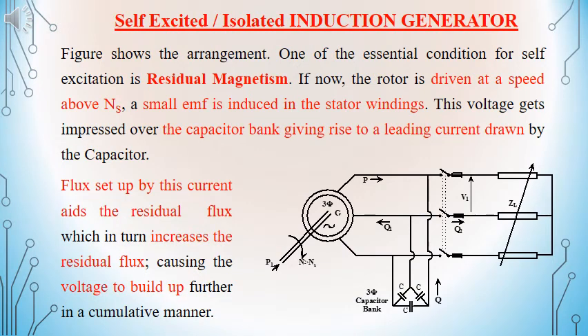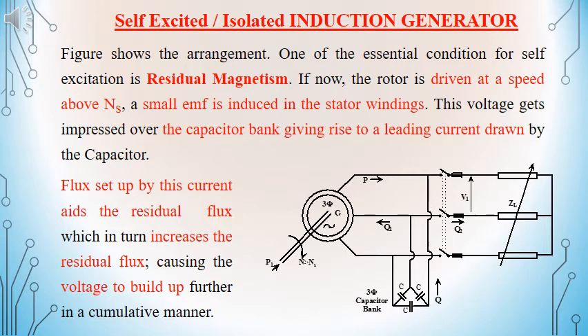One essential condition in the case of self-excited induction generator is that it requires residual magnetism for self-excitation. When the induction generator is driven at a speed above the synchronous speed, because of the residual magnetism, there will be some amount of EMF induced in the stator winding. This voltage will be impressed over the capacitor bank and will allow a leading current to circulate. The flux set up by this leading current will be aiding the residual flux, and because of the same, the voltage that is built up will be increasing.